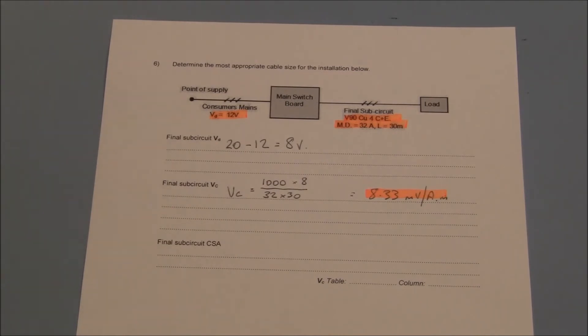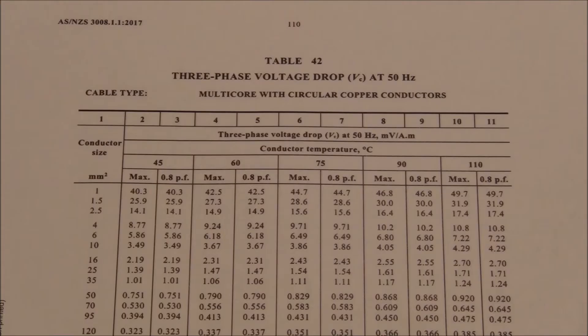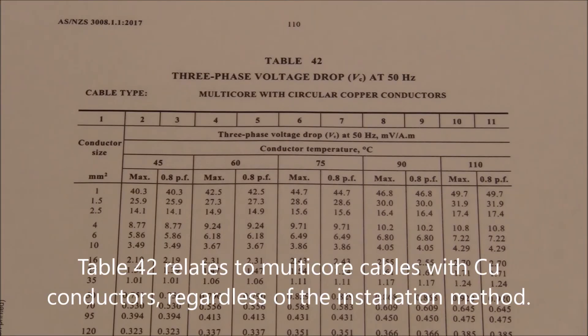This means that our selected cable can have a voltage drop of no more than 8.33 millivolts for every amp flowing through it for every metre of its length. Table 42 is the appropriate table for multi-core copper cables.